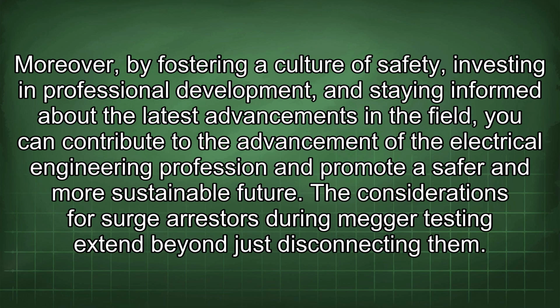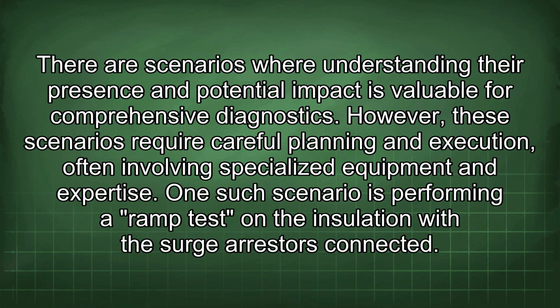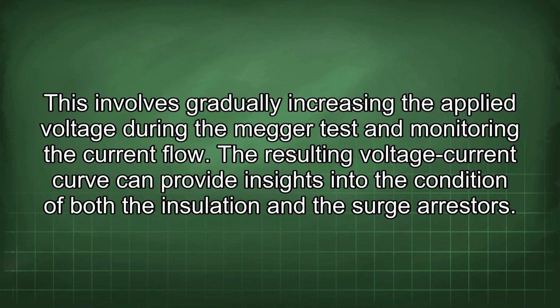The considerations for surge arrestors during Megger testing extend beyond just disconnecting them. There are scenarios where understanding their presence and potential impact is valuable for comprehensive diagnostics. However, these scenarios require careful planning and execution, often involving specialized equipment and expertise. One such scenario is performing a ramp test on the insulation with the surge arrestors connected. This involves gradually increasing the applied voltage during the Megger test and monitoring the current flow. The resulting voltage current curve can provide insights into the condition of both the insulation and the surge arrestors.